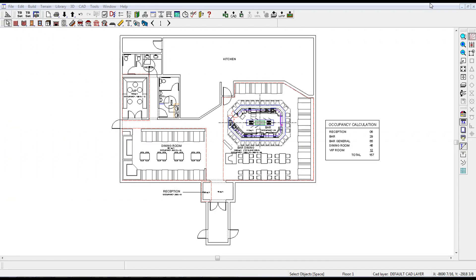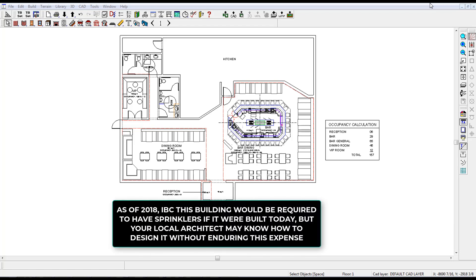The building code is constantly evolving. According to my good friend, architect Tom Kuhn of CSK Architects, as of 2018, IBC now requires sprinklers for businesses in occupancy A2 that serve alcohol. Any new or existing modified fire area over 1,500 square feet would be required to have sprinklers if you want to meet the current code without implementing workaround design parameters available in Chapter 34. Always consult your local architect.